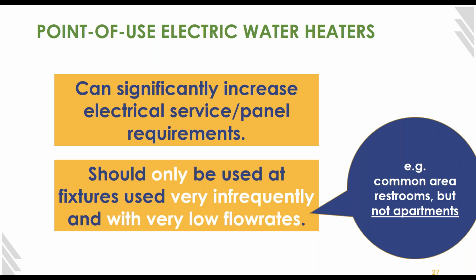First, they can significantly increase your electrical service and panel requirements, because these heat all of the water up instantly—there's no tank. So when you call for hot water, it's heating all of it up immediately with pure electricity. That can get pretty expensive, and you often need bigger wires and bigger electrical service.